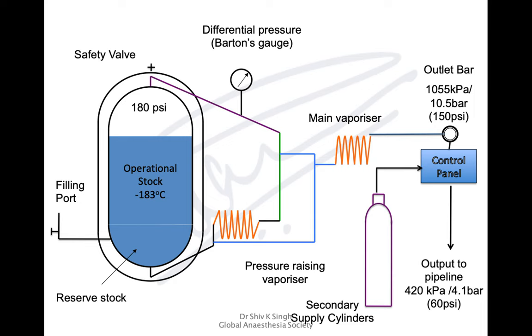The gases pass through a main vaporizer at very high pressure — around 1,055 kPa, 150 psi, or 10.5 bar — then are brought down using pressure regulators to 4 bar (about 60 psi) for output to the pipeline. This pressure reduction happens within the manifold room.